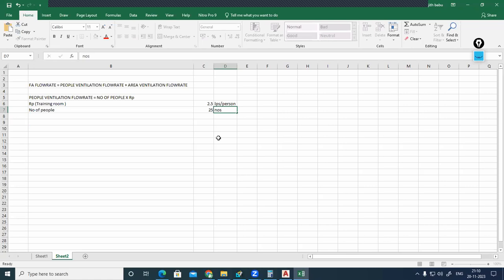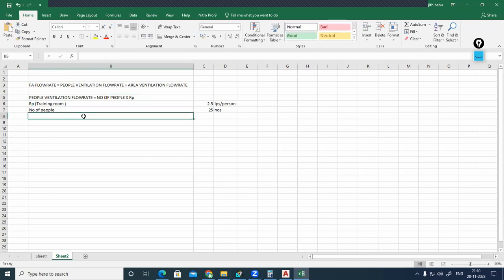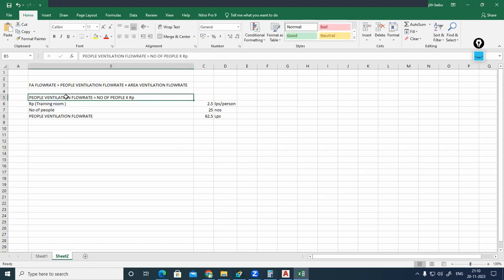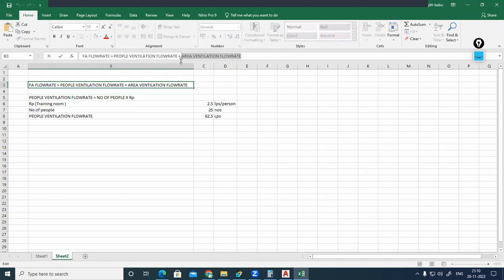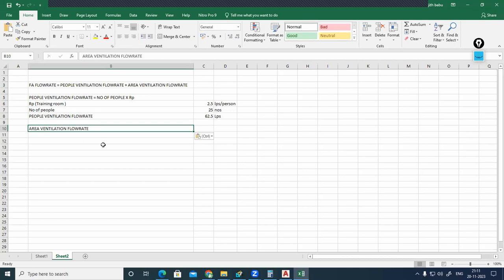Okay, 25 number. Now we can find the people ventilation rate. People ventilation flow rate will be number of people within the building. Number of people within the building is 25 multiplied by liter per second per person value, RP value, 2.5. So 25 into 2.5, you need 62.5 liter per second. That is our people ventilation. The same way, area ventilation flow rate we should find. Area ventilation, you should find. Area ventilation flow rate will be space area that we are designing, or the floor area of space.